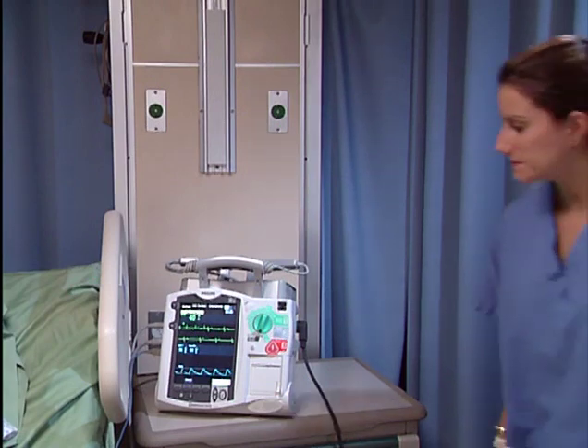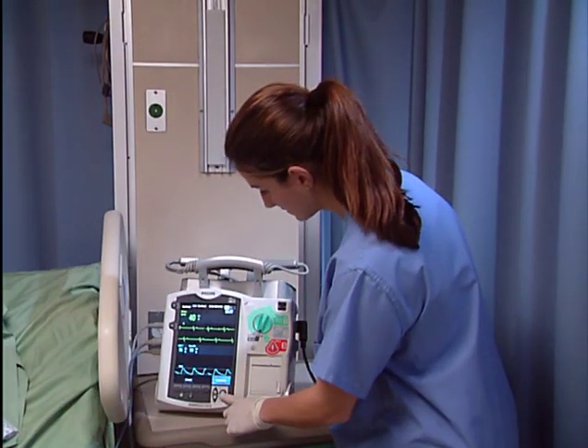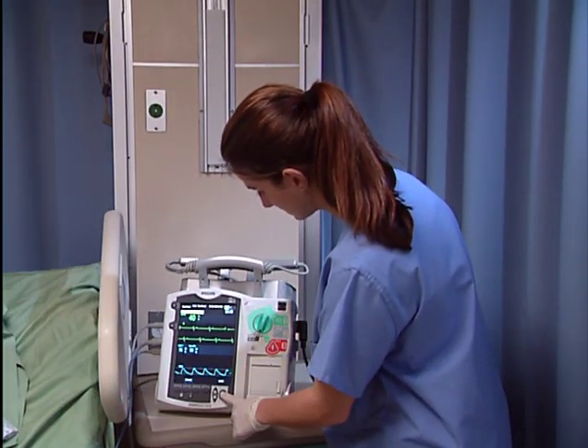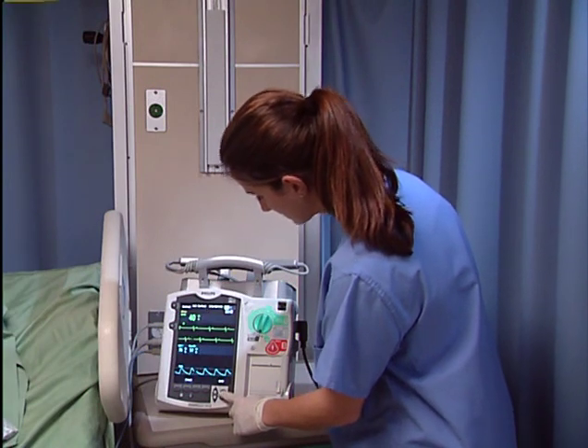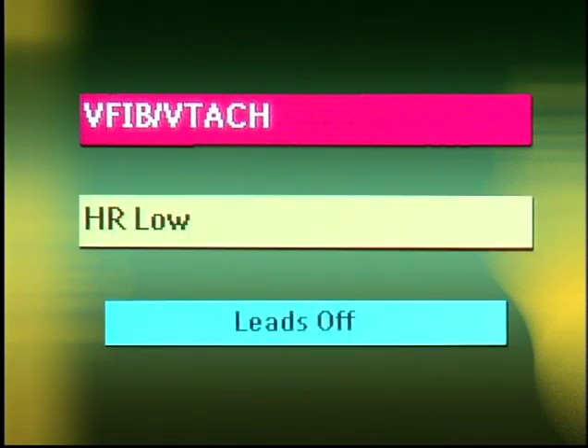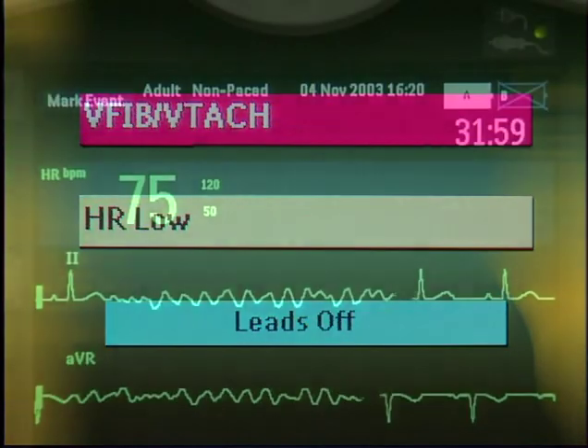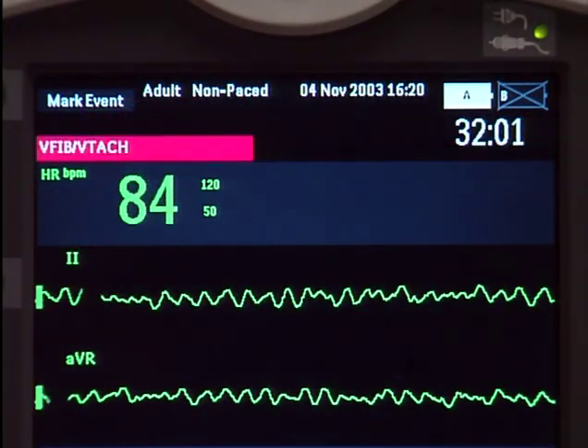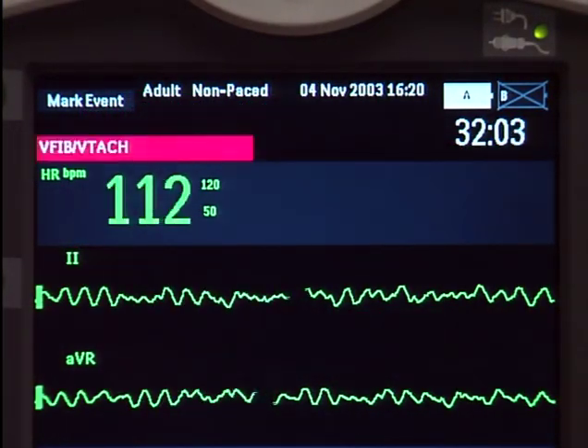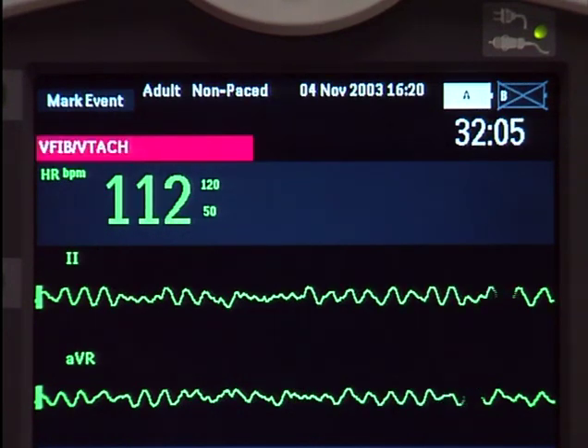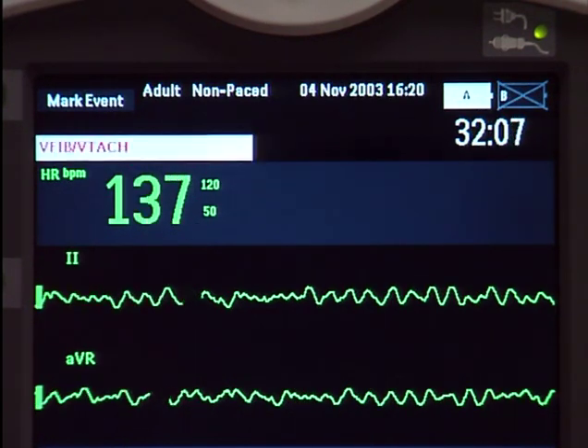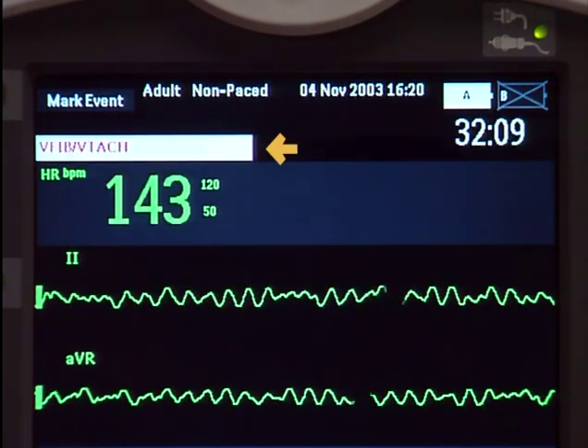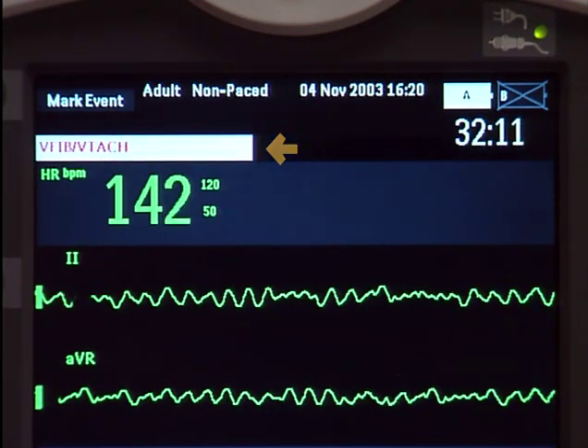With each measurement that the MRX monitors, there are alerts to advise when your patient's condition requires attention. Specifically, there are 3 alert levels: red alarm, yellow alarm, and INOP message. A red alarm warns of a life-threatening condition, such as asystole or ventricular fibrillation. The cause of the alarm displays here with a red background and sounds like this.